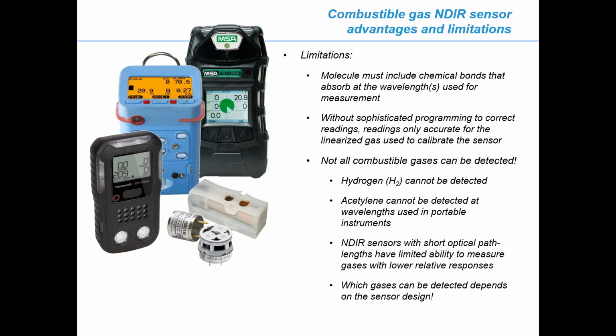If you talk to some other manufacturers, they will point out that, well, that same CO sensor that responds to hydrogen will respond to acetylene. Well, that's true. But if you expose that CO sensor to acetylene, yeah, it'll show an immediate high response. It can take 24 or 36 hours for that response to clear back to zero. So you don't want to plan on doing that on a regular basis. If you have LEL range acetylene, talk to us and we'll set the instrument up in a way that actually measures it.